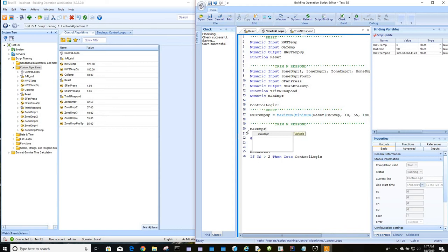This would be a pretty neat spot to use the program we made for the for loops, where you get a quorum, and then you can identify zones that are outside of a certain tolerance range using the standard deviation, and you can identify rogue zones like that and then take them out of the calculation, or programmatically start to change your trim or start to change your set point and so on.